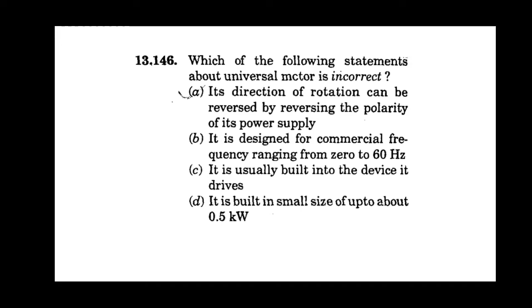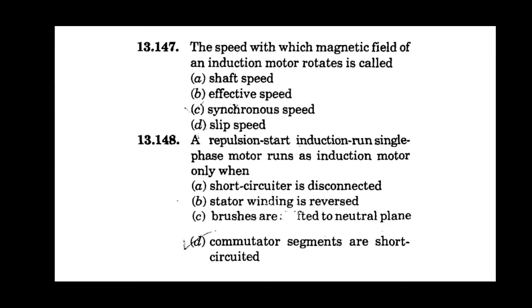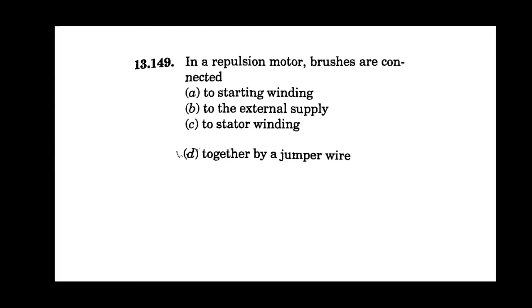The speed at which magnetic field of an induction motor rotates is called synchronous speed. A repulsion start induction run single phase motor runs as induction motor only when commutator segments are short circuited. In a repulsion motor, brushes are connected together by jumper wire. A motor gets overheated due to all of the above.